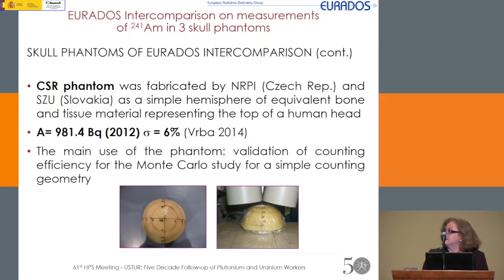Finally, this simple phantom was constructed especially for this exercise. It's a hemisphere of equivalent bone and tissue material representing just the top of a human head with an activity around 1,000 becquerels. And the main purpose of this phantom was the validation of the counting efficiency obtained with the Monte Carlo study for a simple counting geometry.